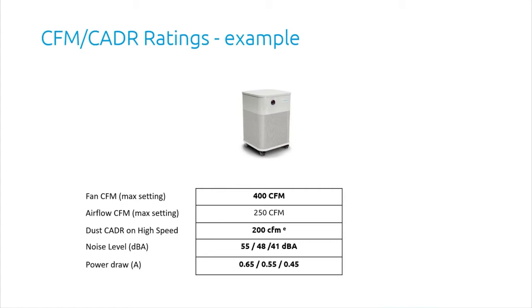So you can see that what you care about is probably the CADR more than anything. The actual is super important. What you care least about is what the fan rating is. So don't undersize the unit by using the wrong specification. And I mentioned that CFM is always a trade-off with noise levels and power draws. Some people think, oh, I'm going to need to change my panels and do a bunch of electrical and add stuff. These units most often plug into your wall outlet with no changes to your existing electrical, no changes to your existing panels. They don't draw as much power as people tend to think.